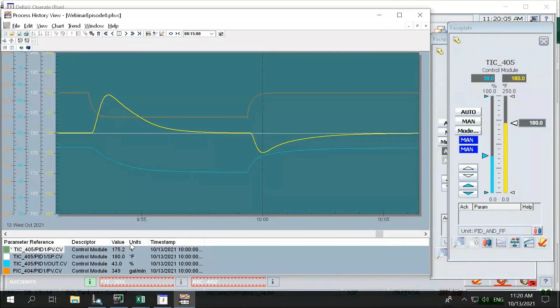As soon as the load flow changed, the feed forward started reacting right away. It didn't wait for the 8 second process dead time, and that helped out the PID controller. Without feed forward, I had about a 9.5 degree deviation between temperature and set point. With feed forward, I had 4.8 degrees variation, almost half. So you can definitely see that being proactive and acting upon a disturbance right away, feed forward can certainly help.